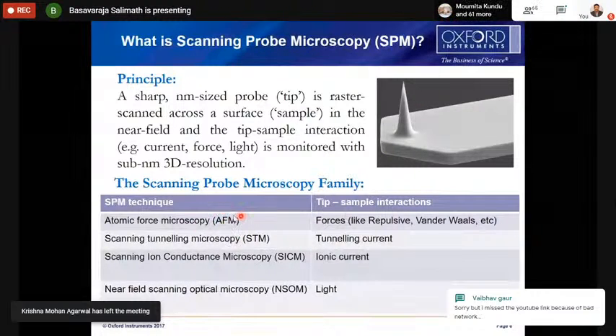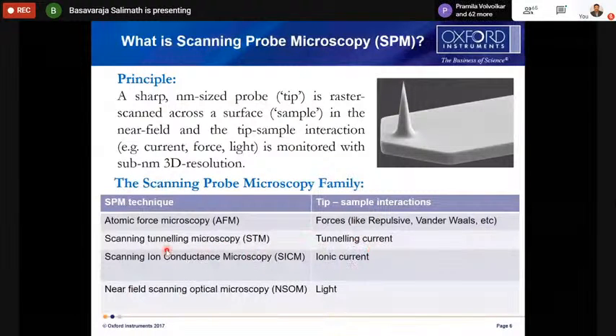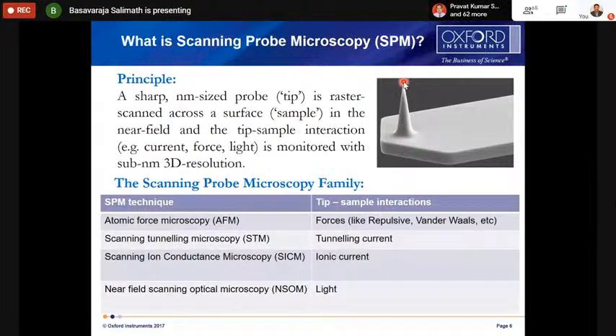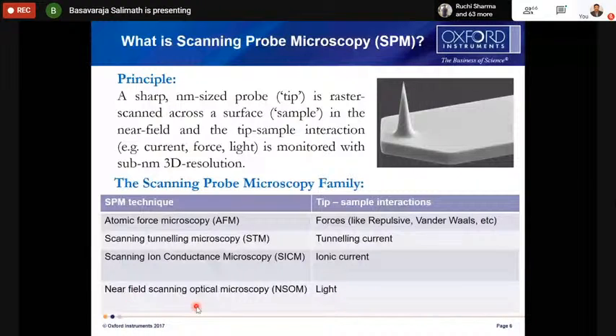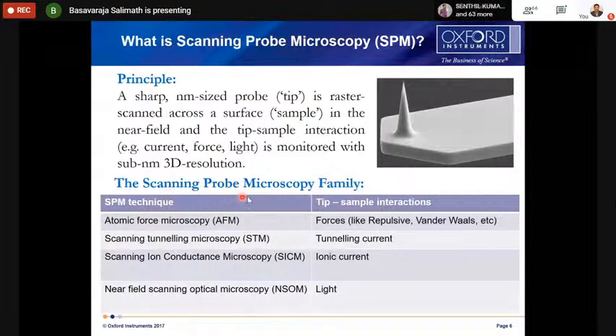If your tip and sample interaction is a tunneling current, then we call it scanning tunneling microscopy. In the same way, if the interaction between the tip and sample is ionic current, we call it scanning ion conductance microscopy. If the interaction is light, we call it near field scanning optical microscopy. These are all techniques that come under the scanning probe microscope family, because in all of them we use a very sharp tip or probe, and we use scanners for the movement.